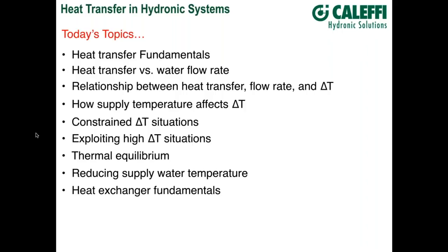You can do a lot of work or move a lot of energy with relatively low flow rates, which means smaller pipes and smaller circulators when you have a high delta T. We'll also look at thermal equilibrium, which says any hydronic system without control intervention will seek a condition where the rate of heat generation equals the rate of heat dissipation.